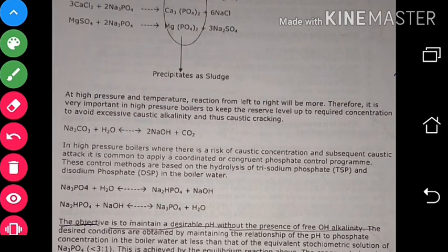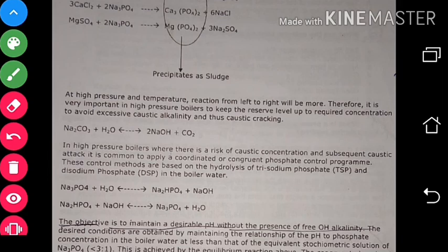The purpose of boiler water treatment: first, to prevent scale formation in the boiler and feed system — we add phosphate for this. Second, to prevent corrosion in the boiler and feed water system — oxygen content and chloride level can form acidic gases, so we add alkalinity. Third, to control sludge formation and prevention of carry-over with the steam.